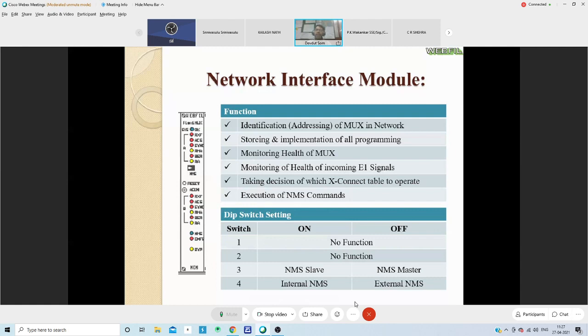Here you can see the functions of the NIM card shown. First and foremost, to identify a multiplexer, you have to set the address of the multiplexer in the NIM card itself. There are two rotary switches, and you can set the address from 01 to 99. In the NIM card there are two rotary switches, S4 and S5.